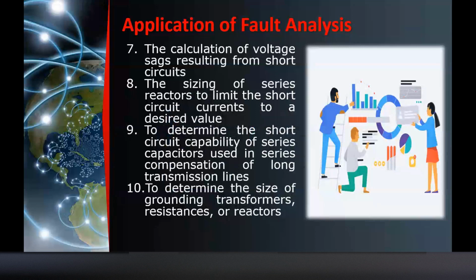So number 7, this is the application of fault analysis, the calculation of voltage sags resulting from short circuit. Actually, it's more on dito na pwedeng pumasok yung motor starting analysis. Because some of the motors, pag nag-run yan, usually 6 to 8 times, but pag nagkaroon ng internal fault, tuloy-tuloy yung tinatawag na inrush current. Magdi-dip talaga or magsasag yung voltage mo. So, yan yung application na yan ng number 7.